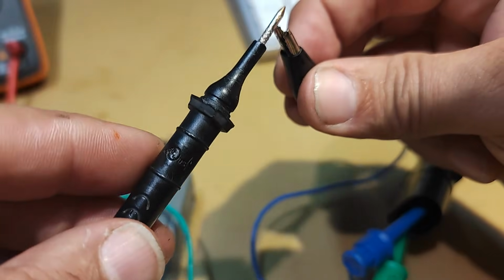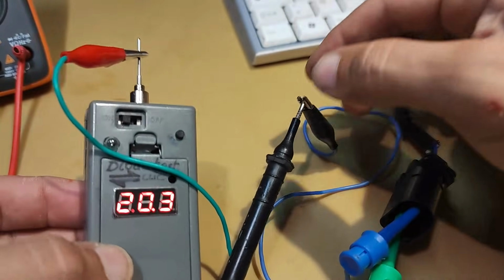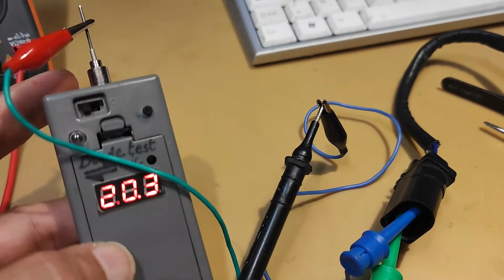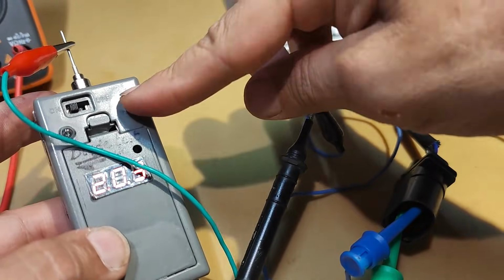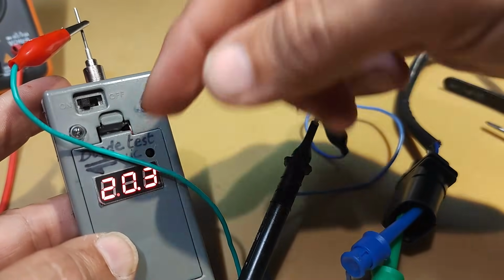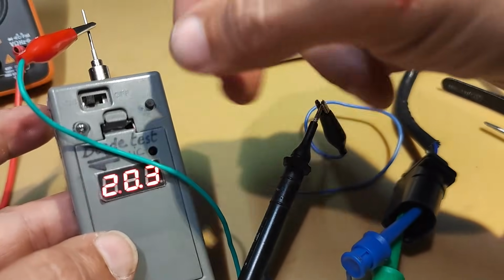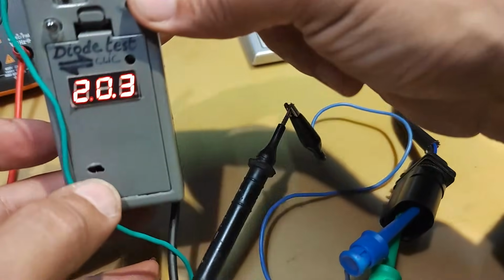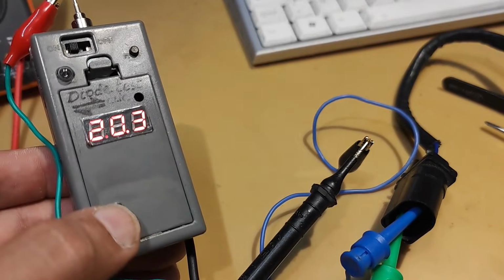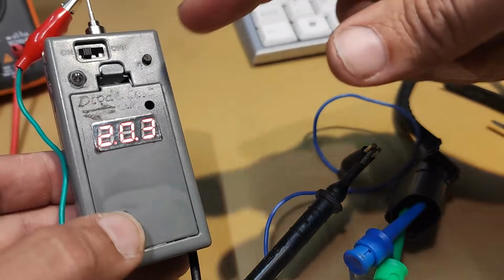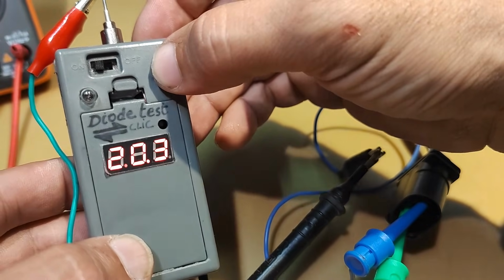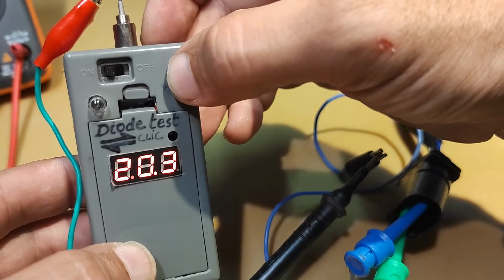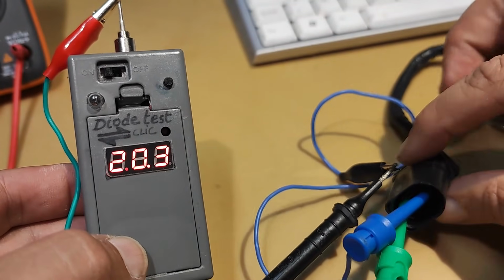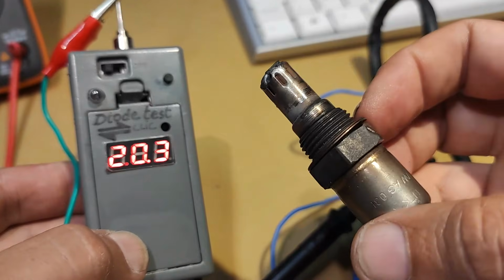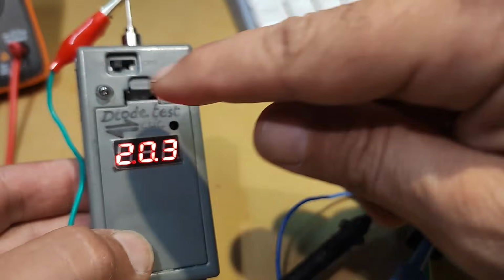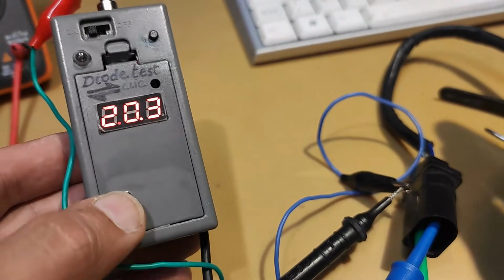And you'll have nothing. If I reverse the current—because this device reverses the current, this is a diode tester with 8 volts—trying to inject this voltage into the pumping current to see if there's any current, and when you push, there's absolutely nothing. So there's something bad with this heating element, because you need current going through this loop.